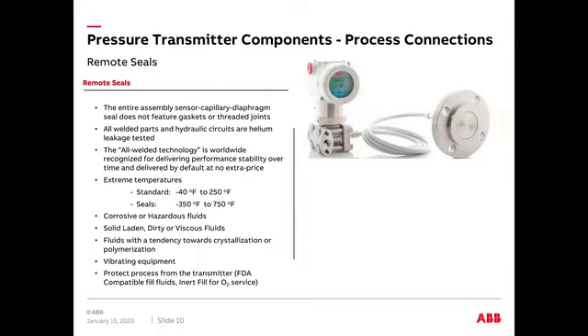With the remote seals, you can get into extreme temperatures. So standard that I was talking about on the previous slide maybe is minus 40 degrees to 250 degrees. But depending on the remote seal you choose, you can get down to minus 350 degrees, all the way up to 750 degrees F. So temperature extremes can be used with the remote seals. There's many different types of remote seal coatings or remote seal metals that can be used if you're in a corrosive or hazardous fluid. If you're in solid laden or dirty or viscous fluids, there's also different types of materials that can be used.